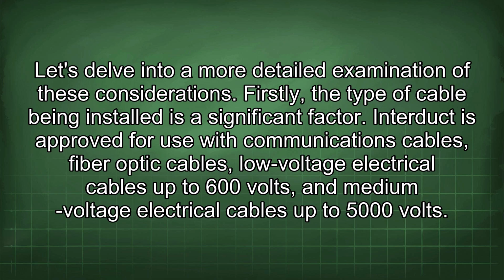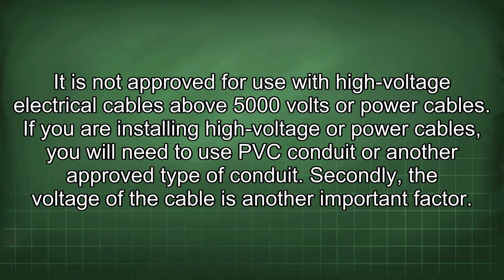Firstly, the type of cable being installed is a significant factor. Interduct is approved for use with communications cables, fiber optic cables, low voltage electrical cables up to 600 volts, and medium voltage electrical cables up to 5000 volts. It is not approved for use with high voltage electrical cables above 5000 volts or power cables.